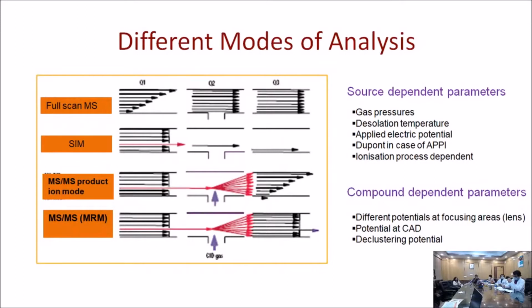But when it comes to MS-MS mode, that is MRM—the fourth panel in this picture shows MRM. You allow all ions to go, then select cortisol alone, which goes to the second quadrupole. I fragment it, and if the fragment is selected at quadrupole 3, this combination gives the highest specificity for a particular ion—only cortisol comes out, nothing else.